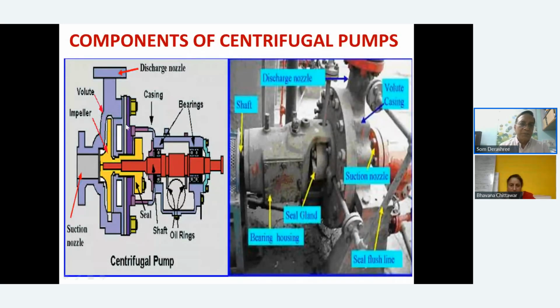A centrifugal pump looks typically like this. You have a suction nozzle, which is the eye of the pump, as it is also called. Then you have a rotating shaft where you have two bearings, which is driven by the motor here. Then you have an impeller. That's mounted on the pump shaft, and the fluid, due to the centrifugal action, gets out into the discharge. And then you have various other components like casings, and you have a seal here, you have a shaft and oil rings, etc. This is how it typically looks.